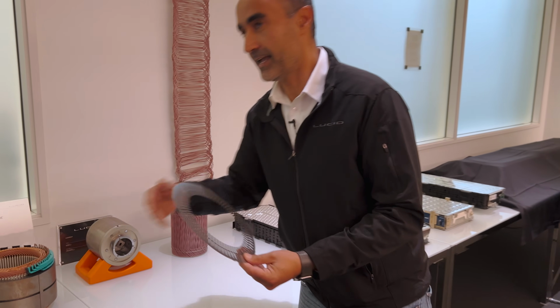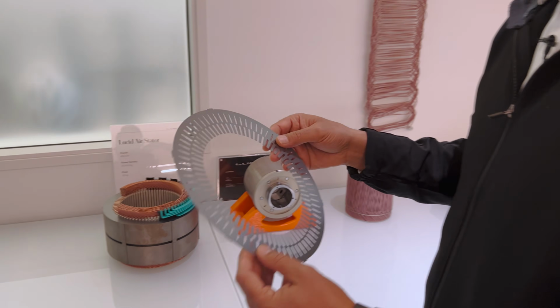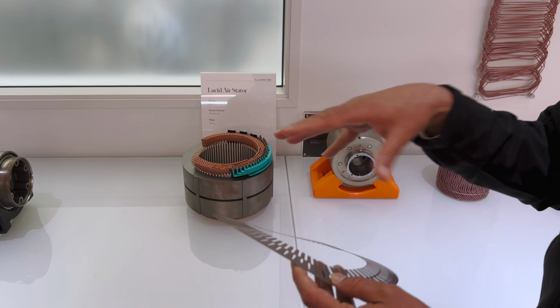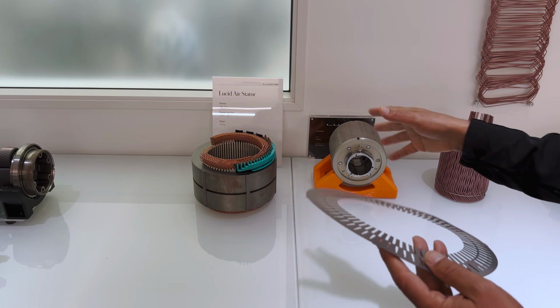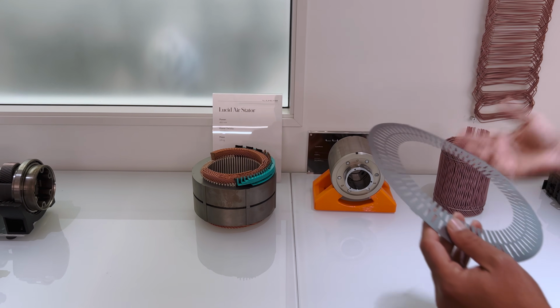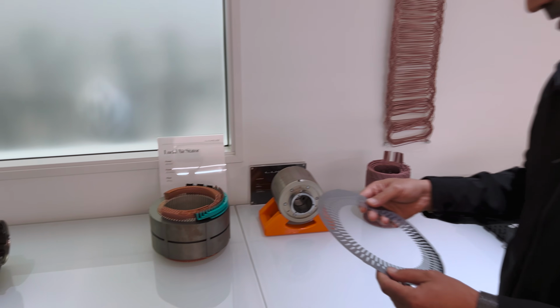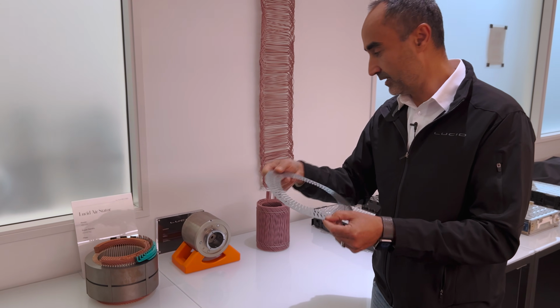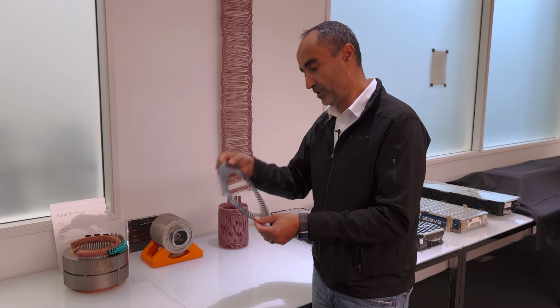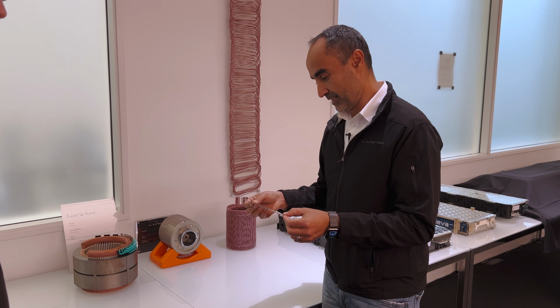The entire stack here, made of about 400 laminations plus, is all stamped in a progressive die, similar to any other stator or motor in the industry. It's a silicon steel, electrical steel lamination with 0.25 millimeter thickness.